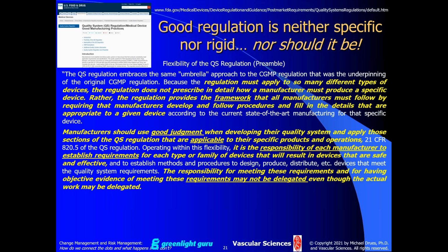The manufacturer should establish requirements for each type or each family of device that will result in devices that are safe and effective, whatever that means. And the responsibility of meeting those requirements and having objective evidence for meeting those requirements may not be delegated, even though the actual work is delegated.